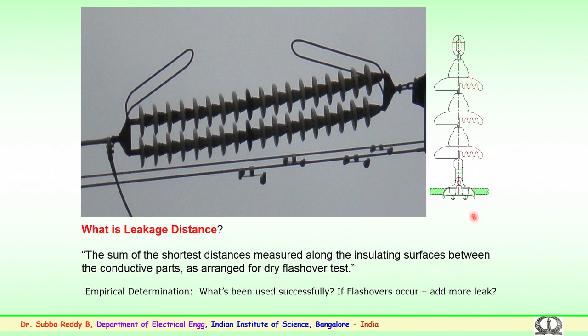The distance from the pin junction completely covering the petticoats or the sheds of the insulators up to the cap portion, this is the leakage distance or the creepage distance, what we call. So, this creepage distance is multiplied by the number of insulators. Neglecting the metal distance, only the creepage distance of all the insulators is summed up, which is known as the leakage distance. So, it is the sum of shortest distances measured along the insulated surfaces between the conductive parts, in case of arranging a dry flashover test.